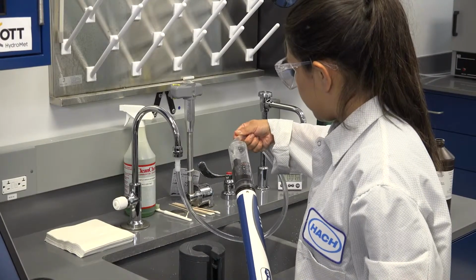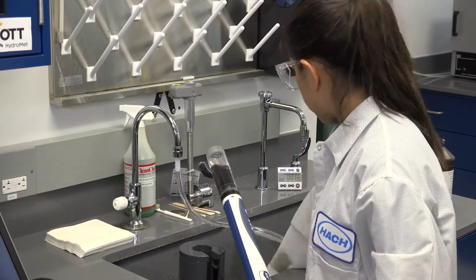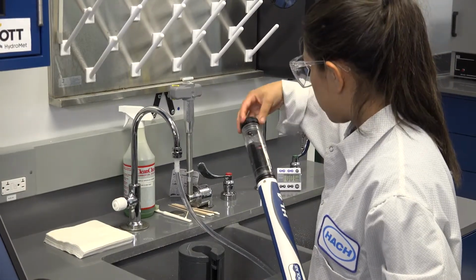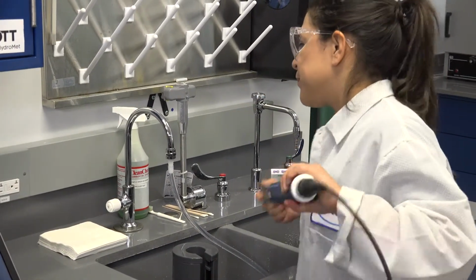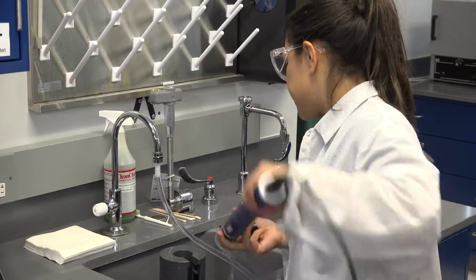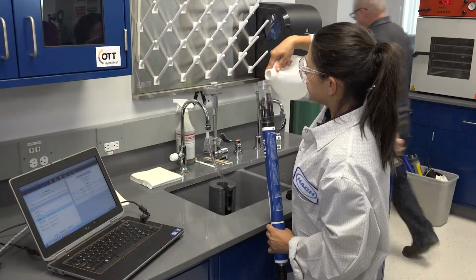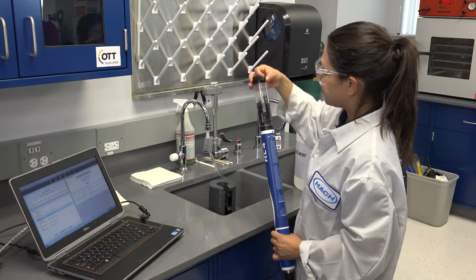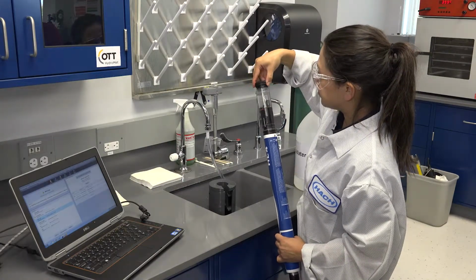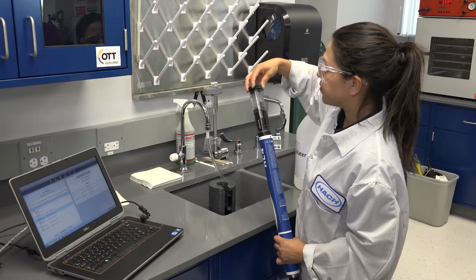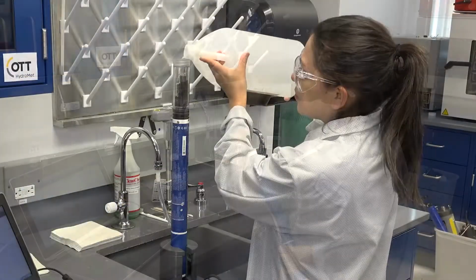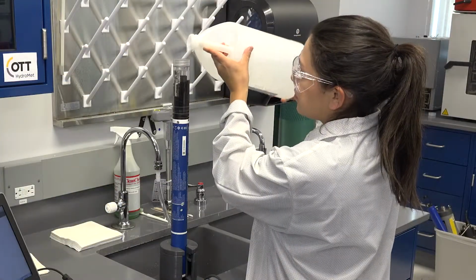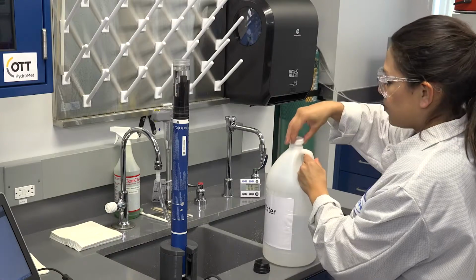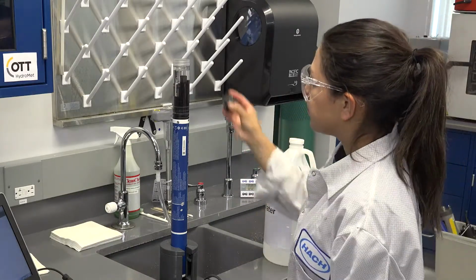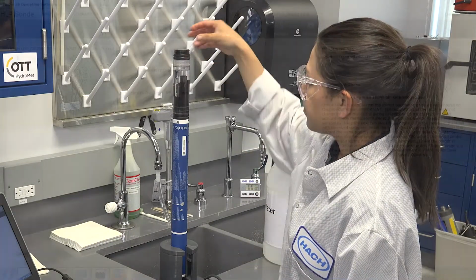Rinse 3 times with deionized water by pouring a small amount of deionized water into the calibration cup, replacing the cap, and shaking vigorously for approximately 6 seconds. Now rinse 3 times by pouring the 100% air-saturated water into the calibration cup, replacing the cap, and shaking vigorously for approximately 6 seconds. Fill the storage cup with the 100% air-saturated water. Do not screw the cap on.